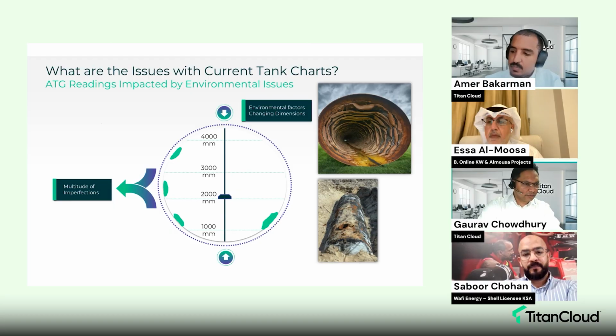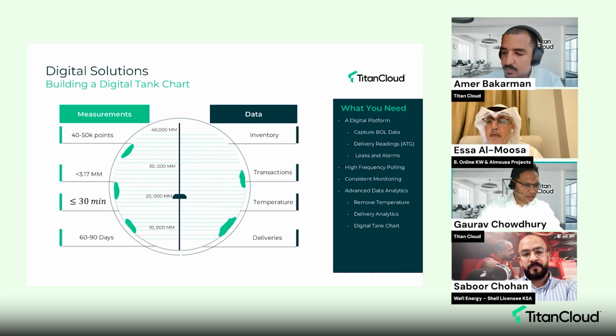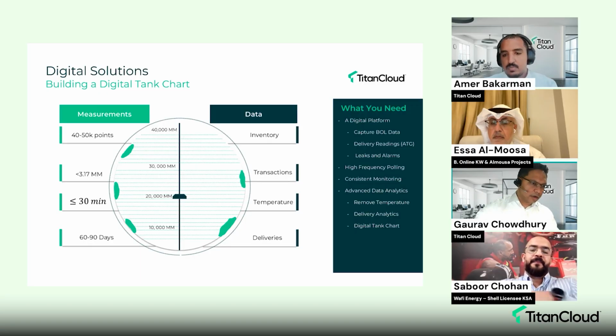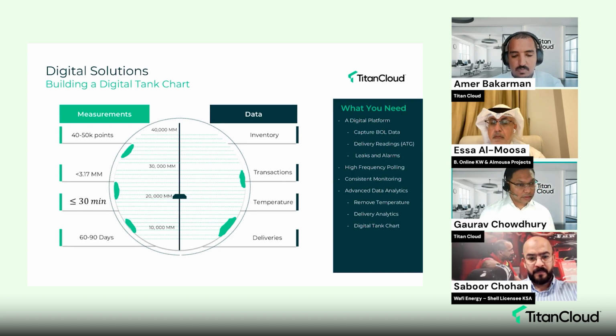We have something called a digital tank chart, which is our internal proprietary calibration process. The way it works is we can capture high frequency data: high frequency inventory data, all transactions, temperature information, and delivery information. Using that data, we can look at the range of how the tank was getting exercised, and based on the data we're seeing, we can start calibrating and provide a better calibration for the tank gauge.